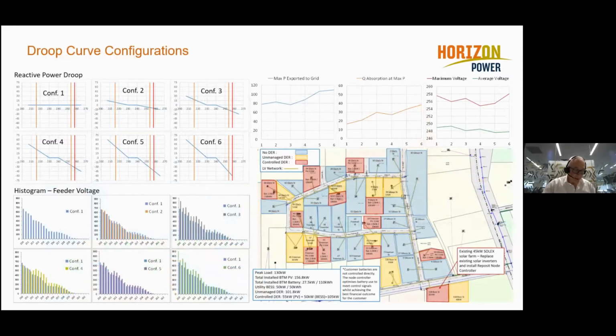So this slide shows on the left-hand side 6 reactive power droop curve configurations that we tested on a group of PV systems all situated on one feeder, which is shown in the map on the bottom right. The map shows the blue properties have no PV systems, the yellow properties have unmanaged PV systems that are not part of the VPP under test, and the red properties have PV systems that are part of the virtual power plant that we're exploring.